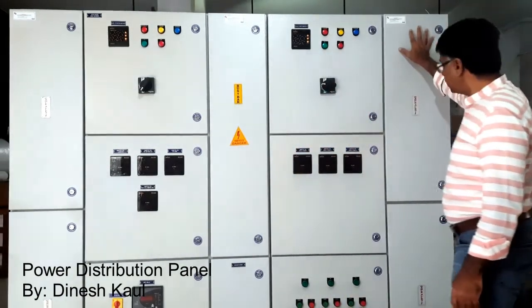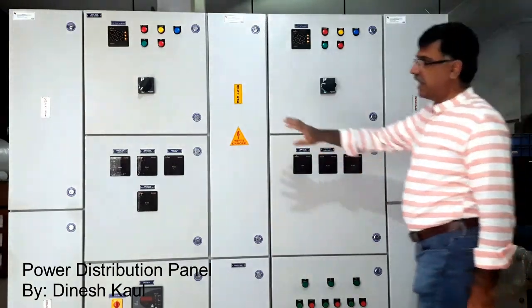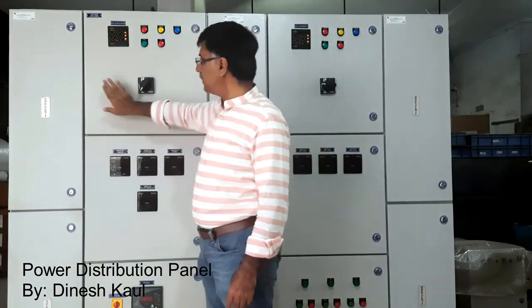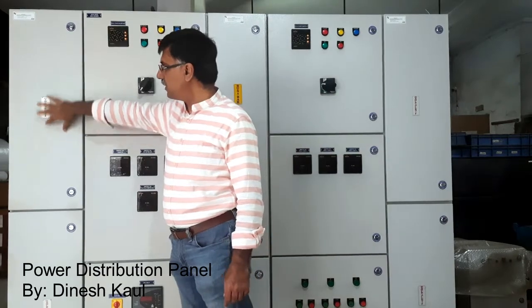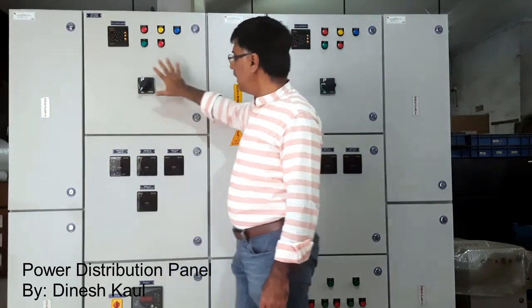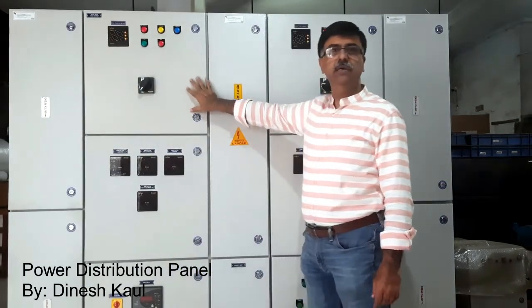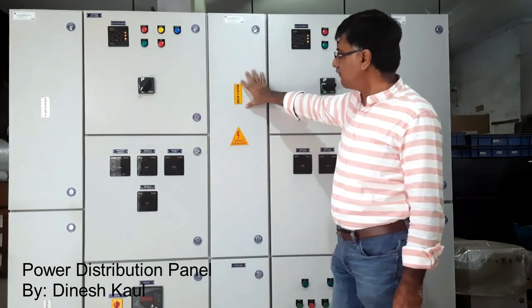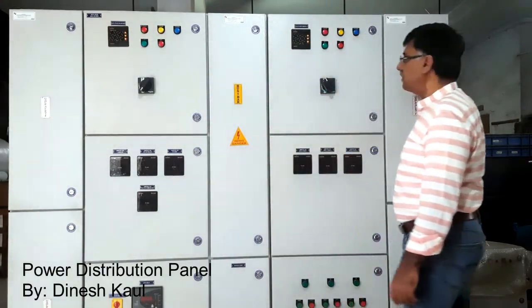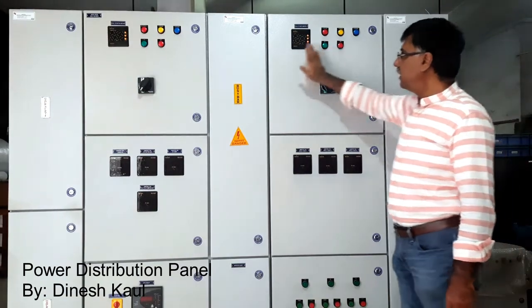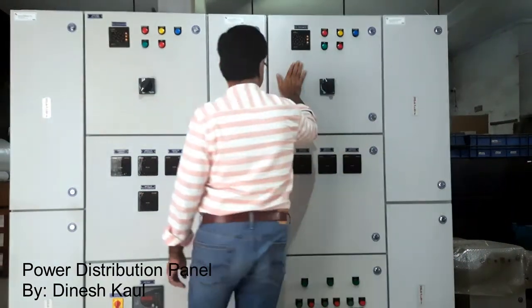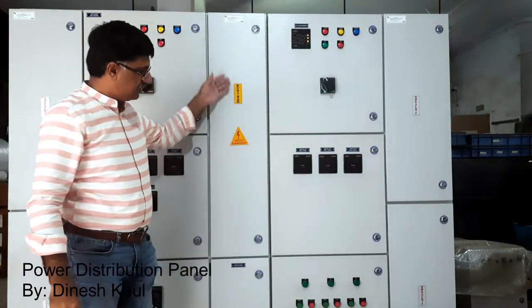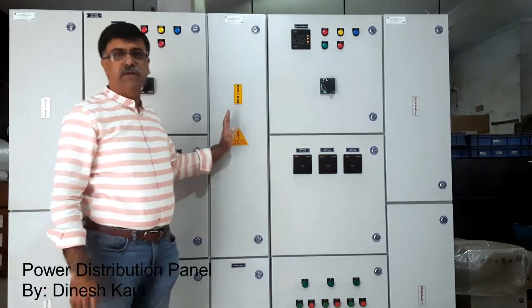For cabling, there is a separate cable alley here and at this end. For example, this main incomer cabling will come in from here, terminate here, and then it will be supplied to the MCCB and from there to the bus bar. And a cable coming from this generator here into this MCCB and then supplying. And all of the load is being supplied from this bus bar.